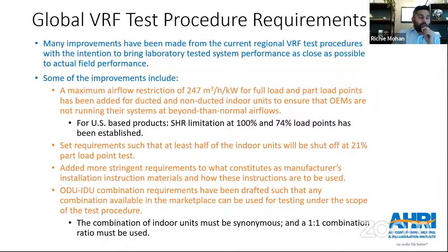And so to that point, the US regulatory process, which we went through just about a couple of years ago, the NGOs, as well as the utility companies, which are power providers, as well as manufacturers, agreed that the VRF ratings in the US have to represent some level of dehumidification. And that's why we've put an SHR cap. The SHR cap is basically 0.82 for 100%, which is 82% sensible heat ratio for the 100% load point. And then it's 85% or 0.85 for the 74% load point.